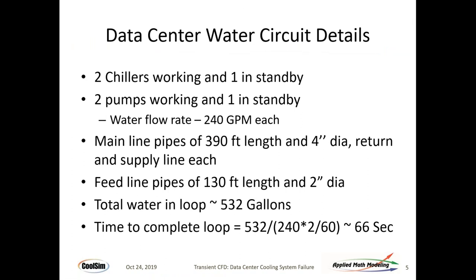In this particular design we had two chillers and two pumps for redundancy. You also need to know how much water is in the loop — specifically the chilled water loop closest to the data center — because that's what holds the heat. These details are different for every data center. In this case: 390 feet of four-inch diameter return and supply, two-inch diameter feed lines, a total of 532 gallons, and a loop transit time of 66 seconds — 33 to get to the chiller and 33 to get back.